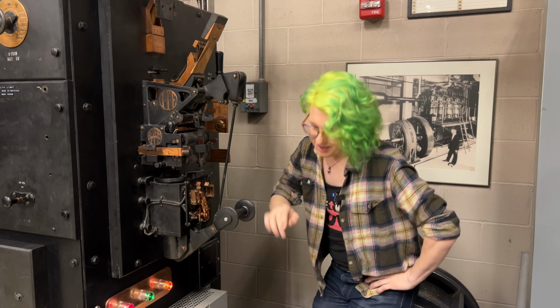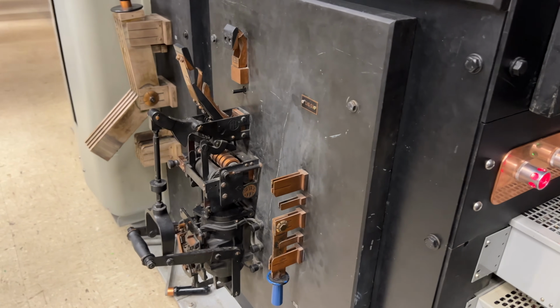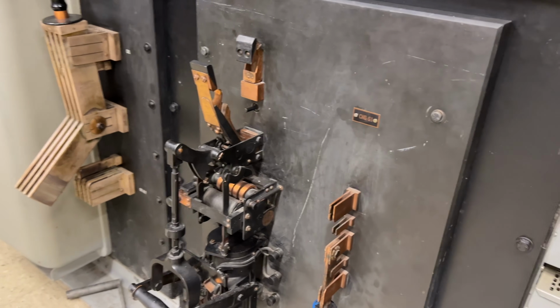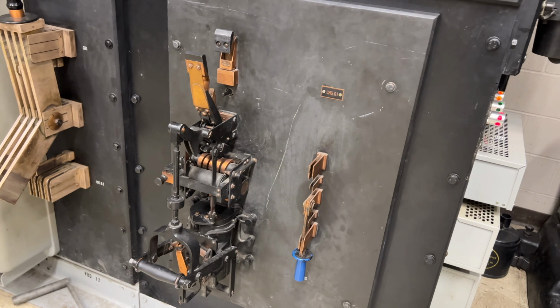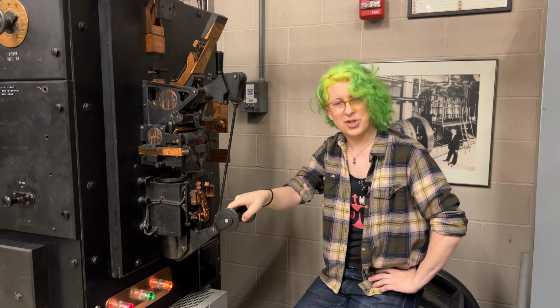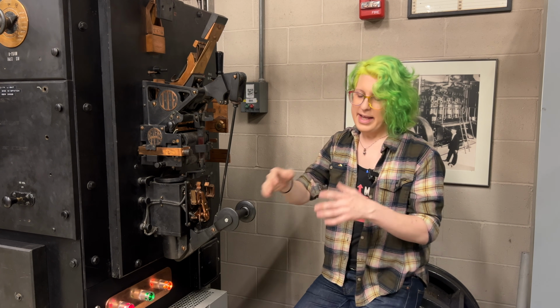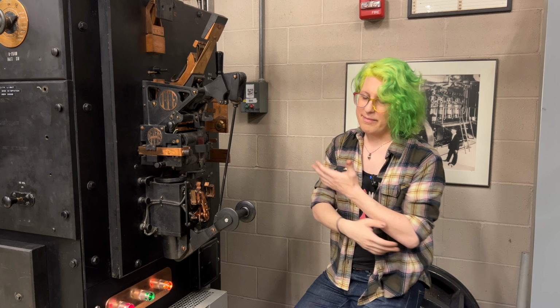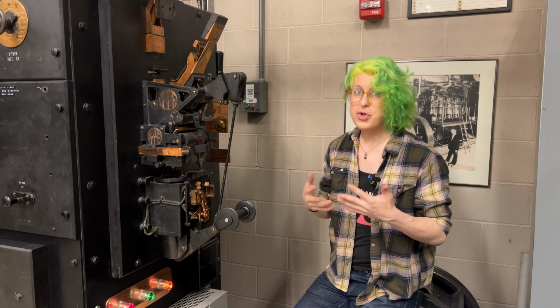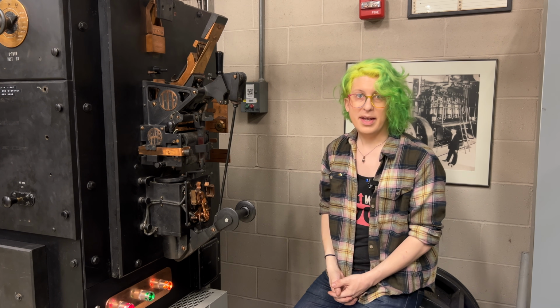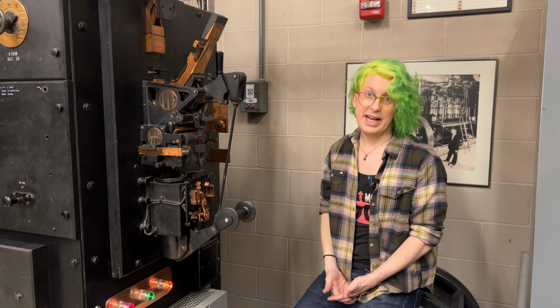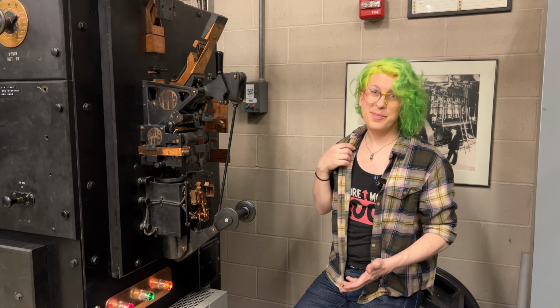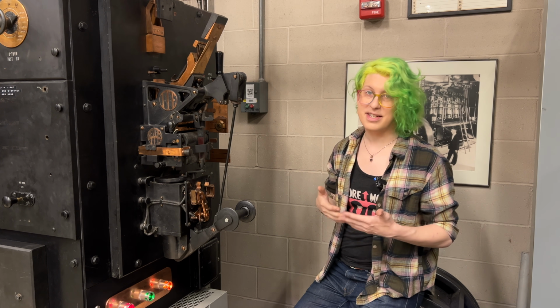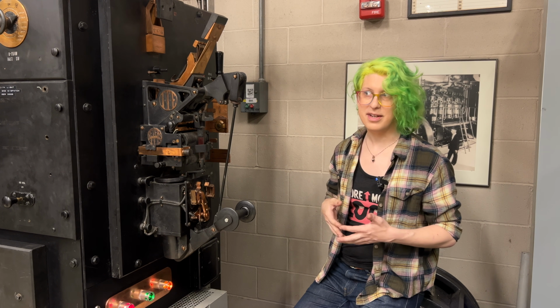This breaker, and the smaller one down there, are designed to protect the batteries against overcharging and loss of generator power. Let's talk about overcharging first. If lead-acid batteries are overcharged, at least 2 really bad things can happen. First, they tend to off-gas. This might not be such a big deal, except that this gas is mostly hydrogen, which is totally explosive.